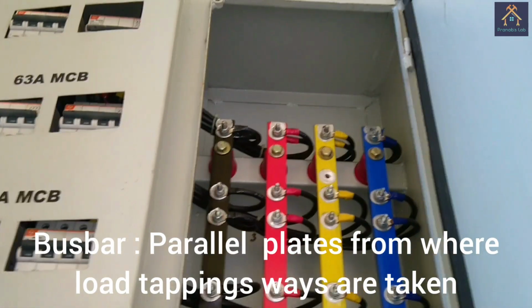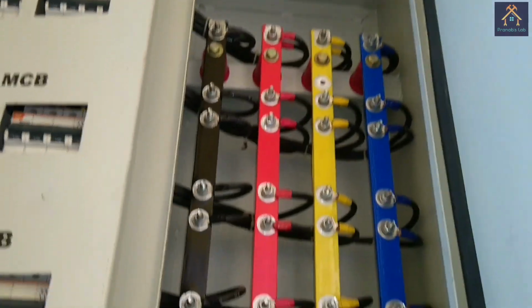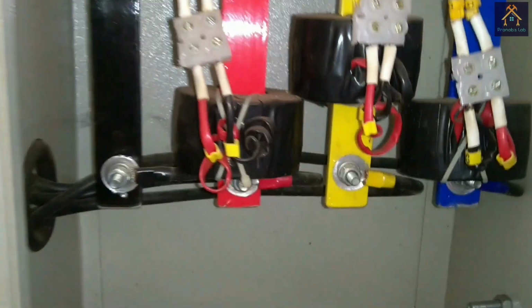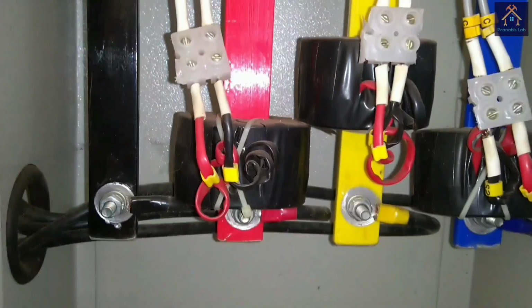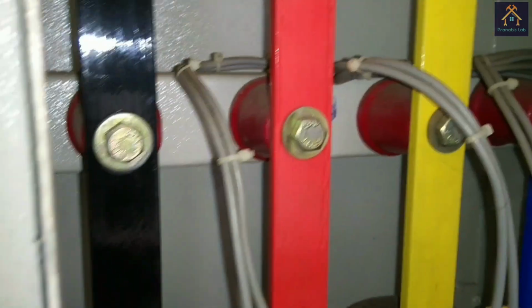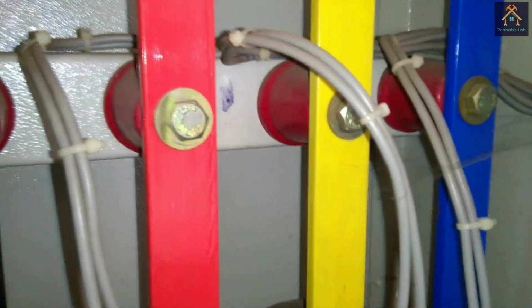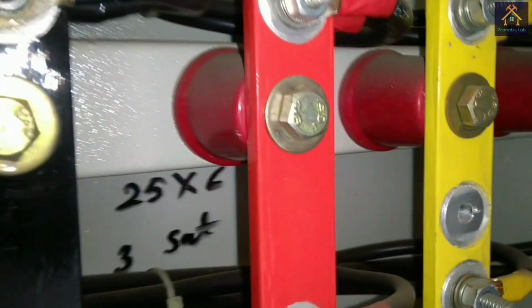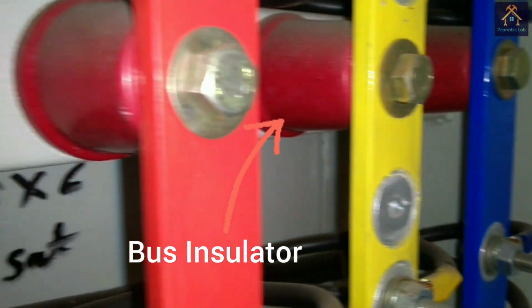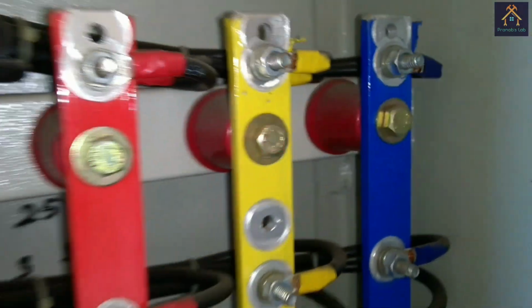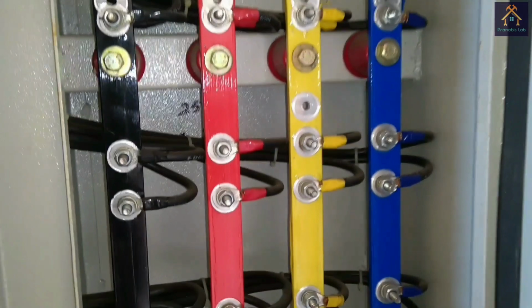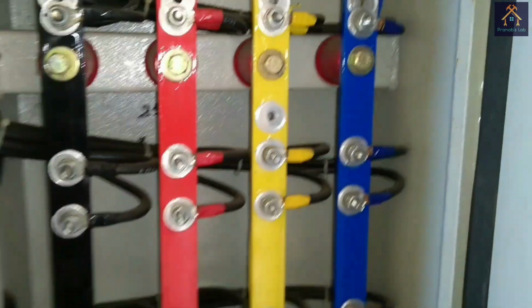4 different color buses are here, that is the red, yellow, blue for 3 different phases and black for neutral. The bus bars are well insulated by different color tapes, so that it cannot touch the body directly. And you can see the bars are mounted on the panel by using 4 different insulators using the nut and bolt. This red color cone-like structure is the insulator which can hold the bars with the panel.